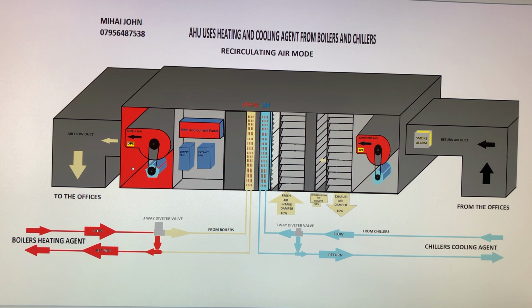You may have a broken motor, the inverter is faulty, the belts are broken, the pulleys are broken, the scroll is broken. But if the fan is running and it's all okay, you have to check the BMS. The BMS can be damaged, or the little clear tubes which collect data about the pressure can be blocked with dust, can be clogged. The same thing applies for this extractor fan. The filters have an analog DPS which reads the value of contamination. That's another story, we'll talk some other time.